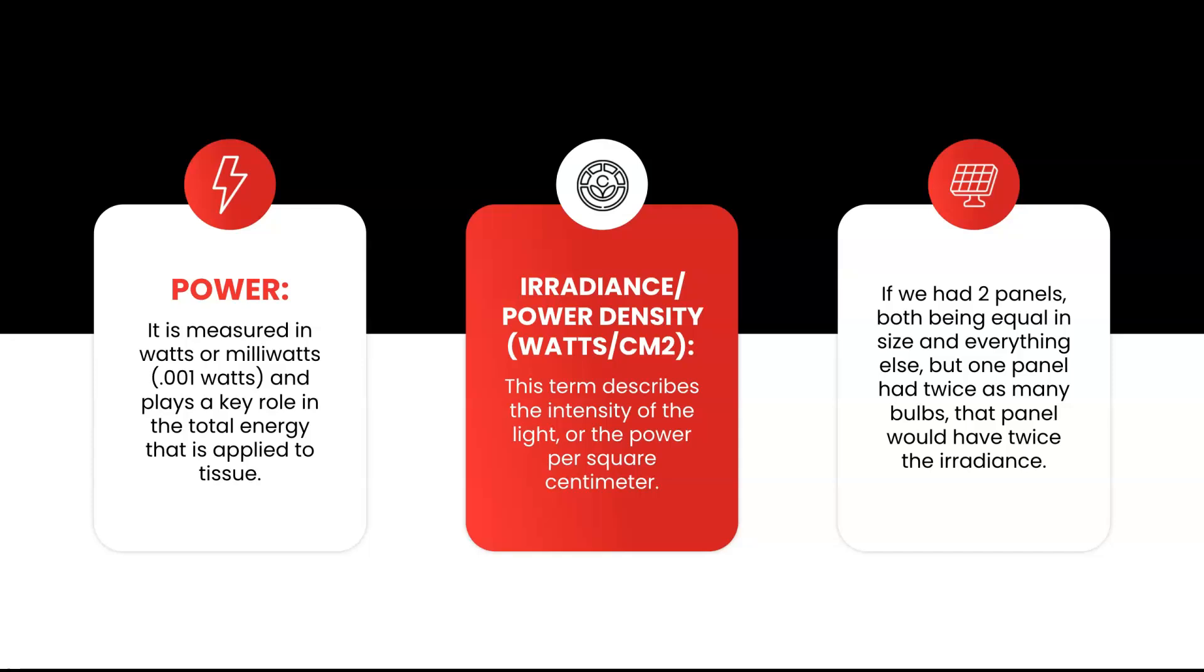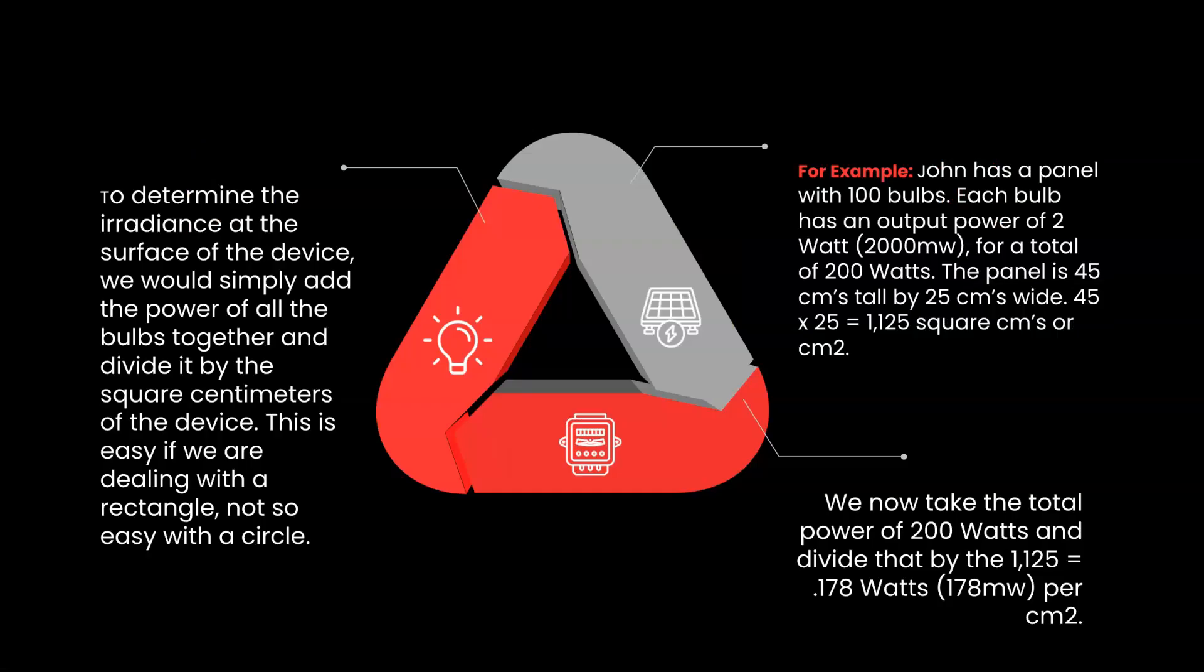This number does not mean much. Irradiance is a more appropriate number as it describes the amount of power over a specific area, typically per square centimeter. If we had two panels of equal size and equal strength in watts per bulb, but one panel had twice as many bulbs, that panel would have about twice the irradiance or twice the amount of power per area. To determine the approximate irradiance at the surface of the device, we would simply add the power of all the bulbs together and divide it by the total square centimeters on the device. This is relatively easy if we are dealing with a rectangular device as opposed to a circular or oval shaped device.